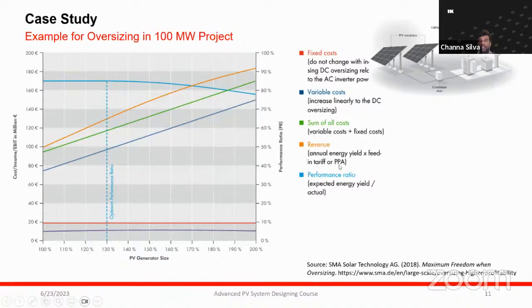If you look at the performance ratio curve, that's purely a technical measure for identifying the optimum. Most cases we've seen show that around 130% oversizing factor provides the optimum from a technical perspective - that's what we as technical people prefer.